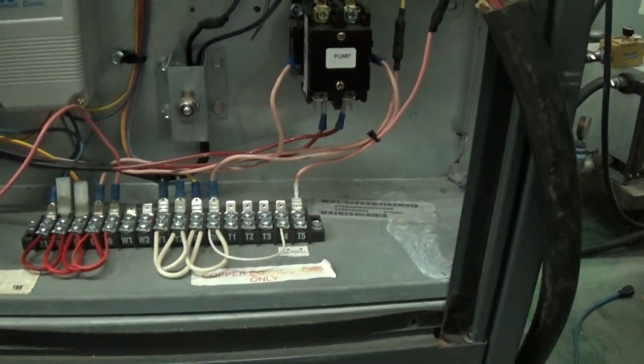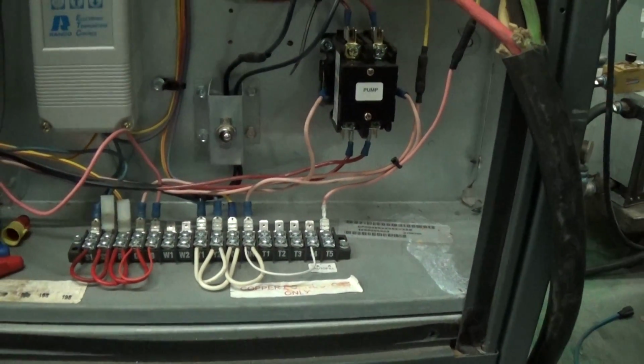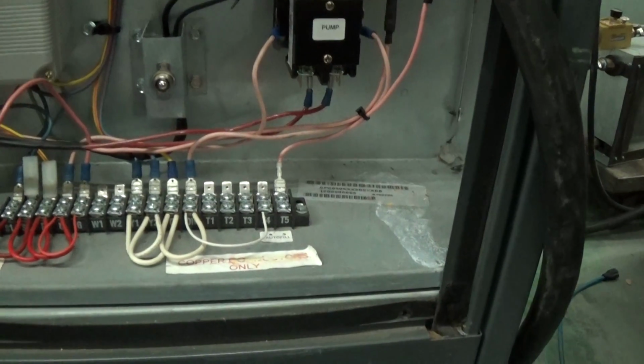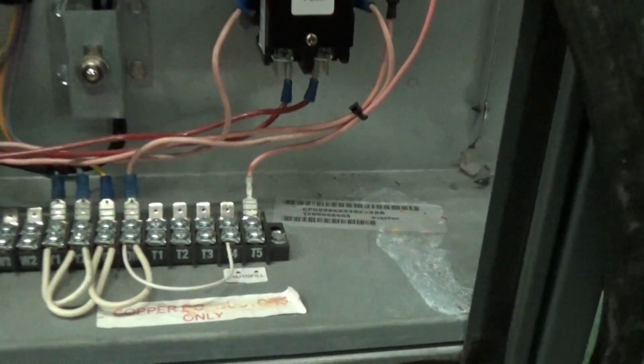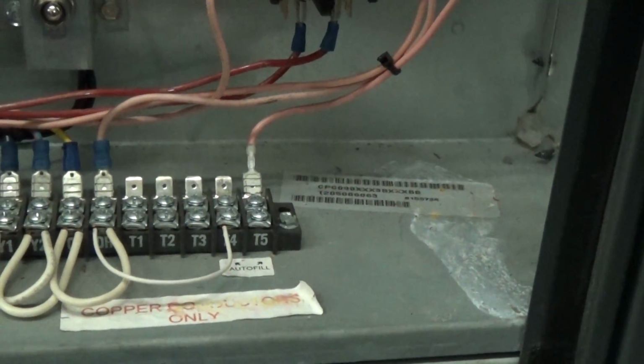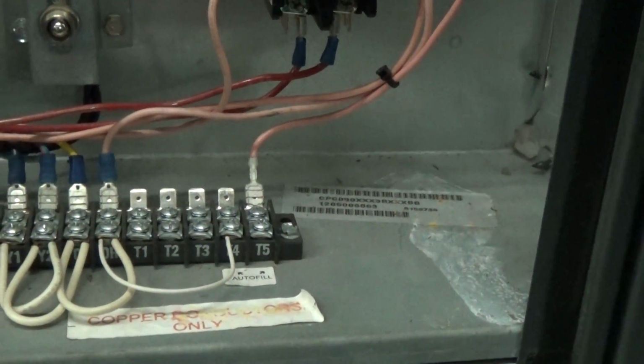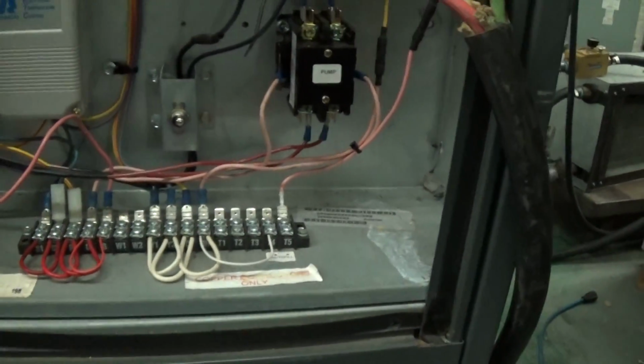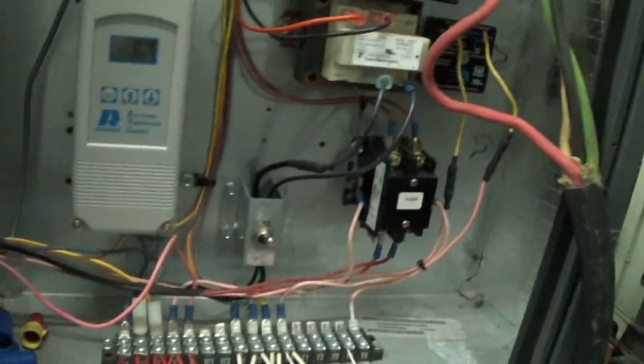In fact, it's dangerous if you add straight water to a glycol chiller. So in this case, what we recommend is you use this feature and tie it into a 24-volt DC buzzer or alarm, and just bring a wire into your office or into your shop.